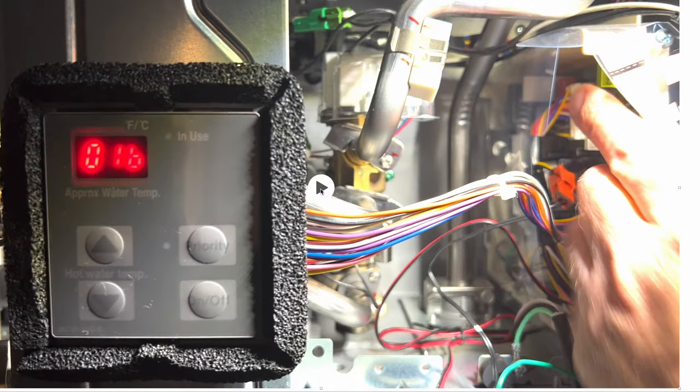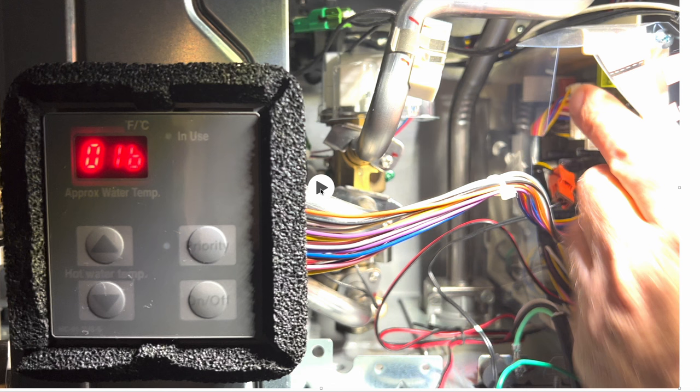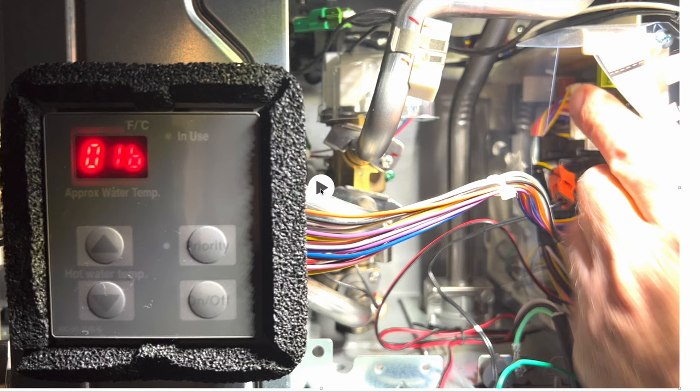Setting O1 is for maximum set temperature. By default, this comes set at A, which limits the max temperature to 120 Fahrenheit. Switching over to O1B raises the temperature to 140 Fahrenheit. To alternate between settings, use arrow up and arrow down. To alternate between selections for each setting, push the on-off button.